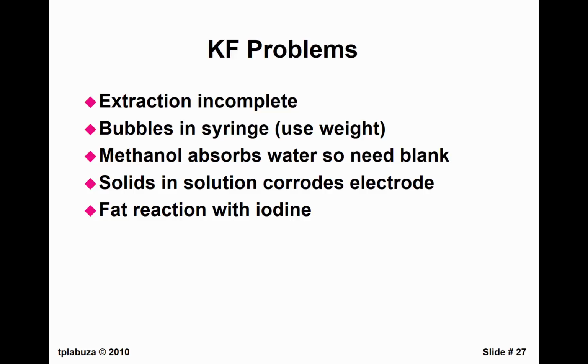Solids in solution can corrode the grid, and they usually last about a year and cost $300 to $400 to replace. You can tell because it starts getting corroded, and you don't want to use it anymore because that changes the resistance. The other thing: if you have high-fat food, the methanol will dissolve some fat as well. If it's unsaturated, you can get a very fast reaction of the iodine across the double bond, so the iodine is used up by the fat, not by the reaction with water. That's a problem.